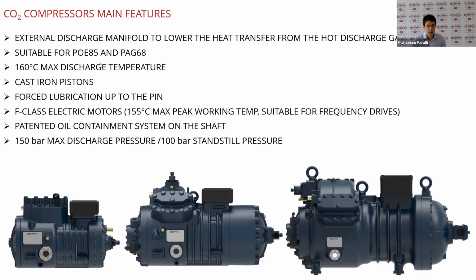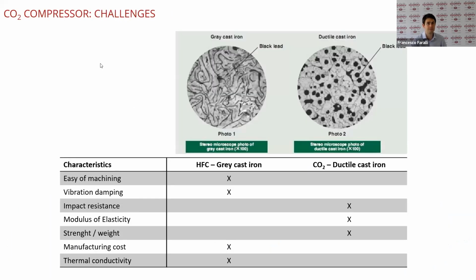application. We have introduced on our CO2 compressor a patented oil containment system on the shaft that is able to reduce the oil carryover by almost up to 80%, depending on the working condition. And actually, this patented oil containment system has been also introduced after the CO2 range, also on our ATEX range for hydrocarbons, and in the end, almost 2 years ago, also on our standard HFC compressors. And the last row is the values of pressure. So we have 100 bar standstill pressure and 150 bar maximum discharge pressure.